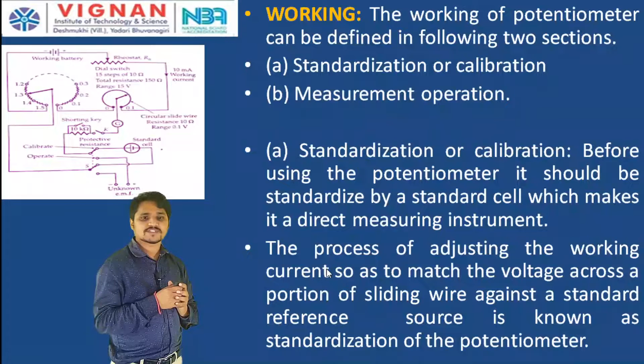And what will we do? We will standardize the potentiometer. Once you connect the standard cell to the potentiometer, by changing the rheostat and the sliding contact we have to obtain the null deflection, that is, the balanced condition, meaning no deflection in the galvanometer. That means by changing this rheostat, this main dial and this slide wire, we have to obtain the balanced condition. What does balanced condition mean? When you adjust the rheostat, main dial and slide wire, the current flowing through the galvanometer becomes zero. That means the voltage in the slide wire is equal to the voltage of the standard cell we connected.